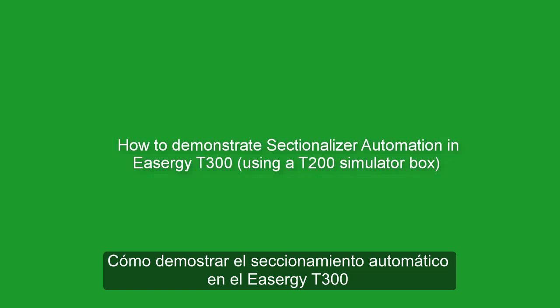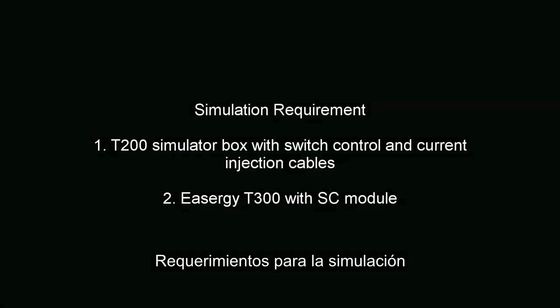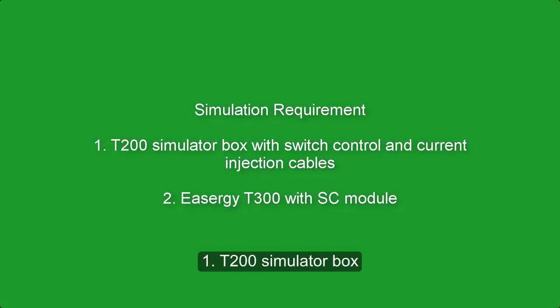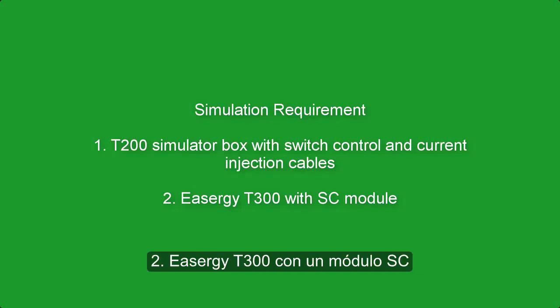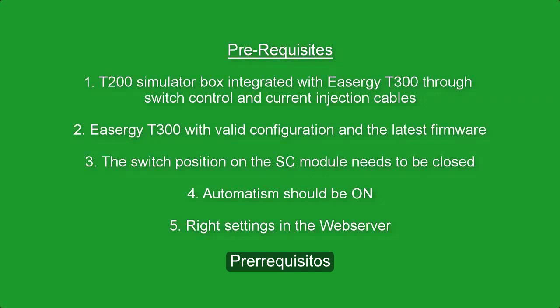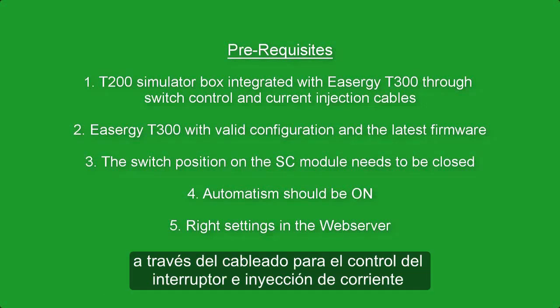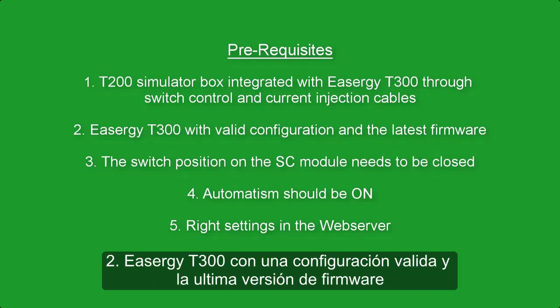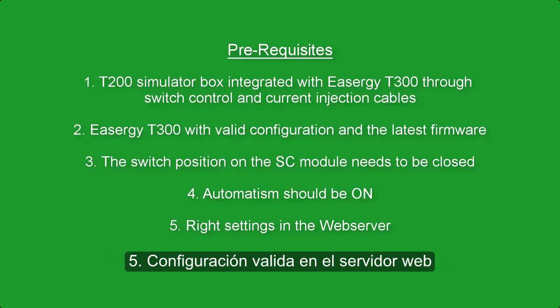How to demonstrate sectionalizer automation in Easergy T300 using a T200 simulator box. Simulation requirements: T200 simulator box with switch control and current injection cables, and Easergy T300 with SC module. Prerequisites: T200 simulator box integrated with Easergy T300 through switch control and current injection cables, Easergy T300 with valid configuration and the latest firmware. The switch position on the SC module needs to be closed, automatism should be on, and right settings in the web server.